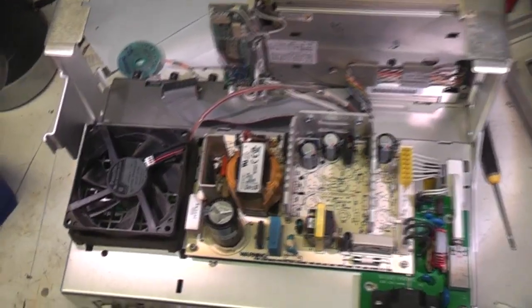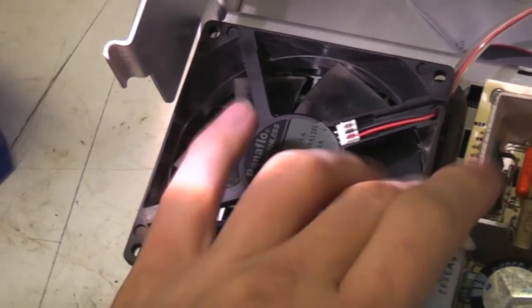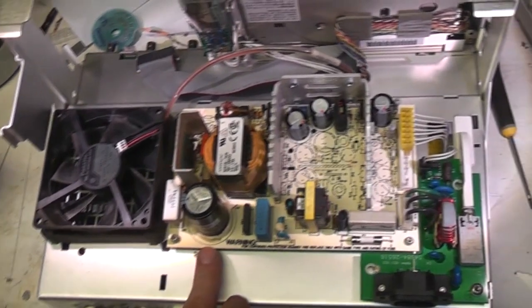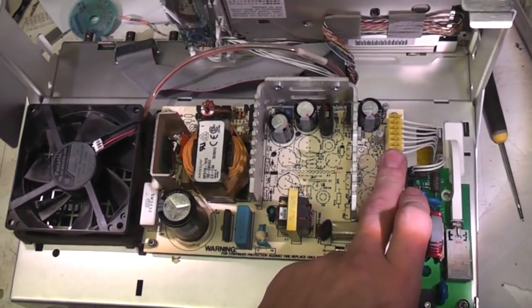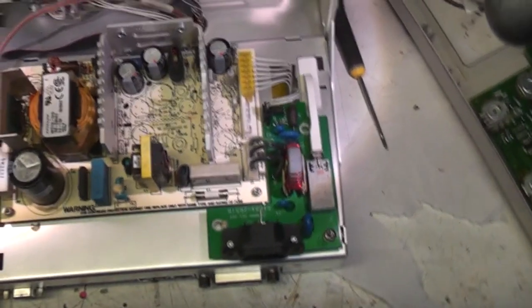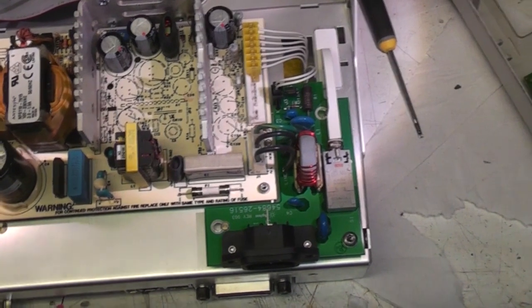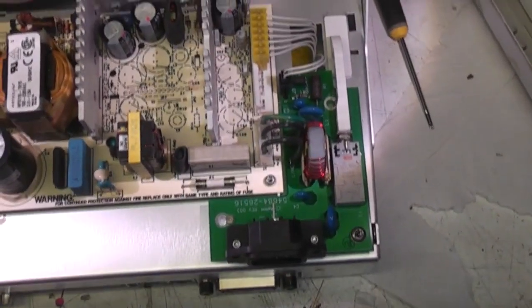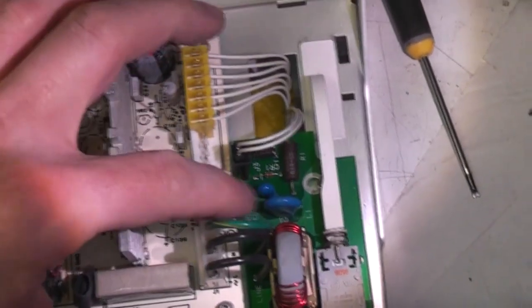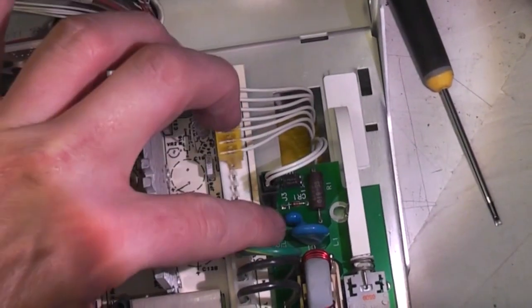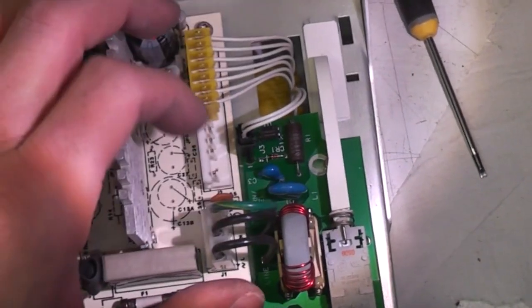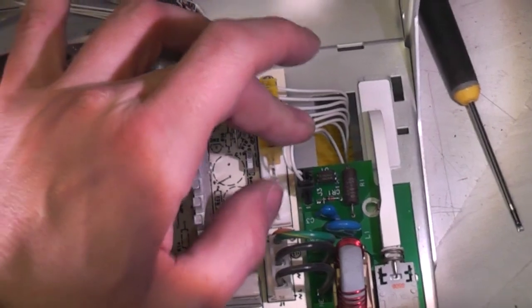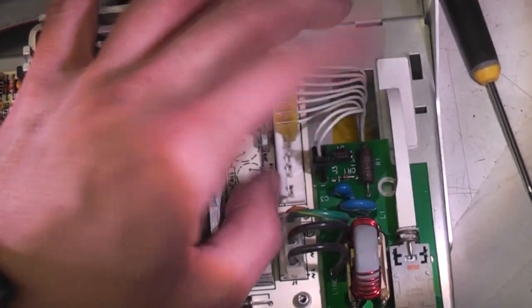This is the top side. Not really a great deal to see here. We've got the fan, actually a fan made by Panasonic. Power supply, fairly standard switch-mode power supply, looks like it's an adaptation of a standard off-the-shelf unit. The only slightly unusual thing is this mains input PCB. One thing scopes need which most other products don't is a frequency reference from the mains. So what they've got here, there's just a little circuit down here, there's an opto-isolator, a power resistor, and a couple of capacitors, so that's just producing a 50 or 60 Hertz, depending on what country you're in, reference for the line mode trigger.